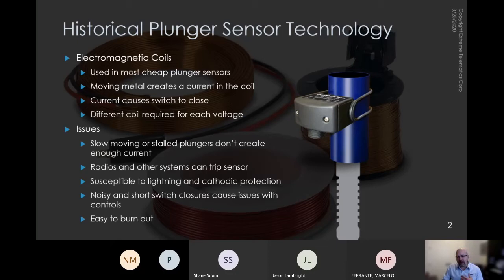Because it has rapid succession closure of that switch, it can confuse control systems. When interfacing with SCADA, polling that sensor signal sometimes gives a noisy closure or a very short duration closure that leads to missed arrivals or false arrivals. And they're easy to burn out—stray voltages or time can burn out those coils.